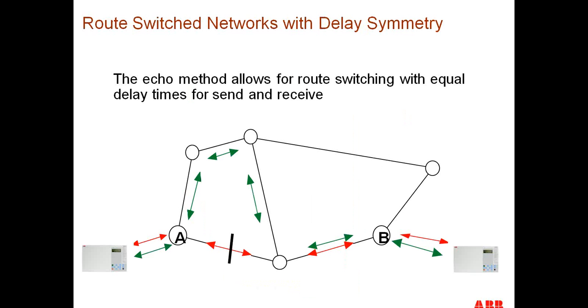When you talk about communications, you can't get around talking about route switching and delay symmetry. Most times you don't have dark fibers to use, and you have to go into a multiplexer, like one gentleman said, a T1 multiplexer or higher level multiplexer, to get the information from one terminal to the other. So if I want to go from terminal A to terminal B, my normal route would be from A to B, but in some cases I may get a break, like you see here between terminal A and this midpoint. And if that happens, my system gets rerouted over this longer path back to B again.